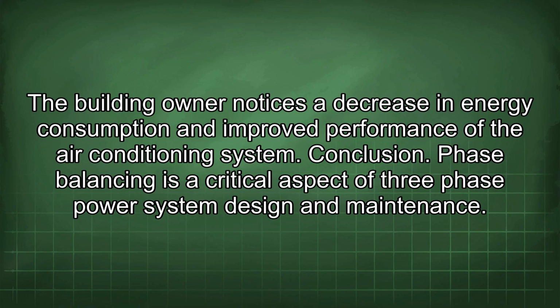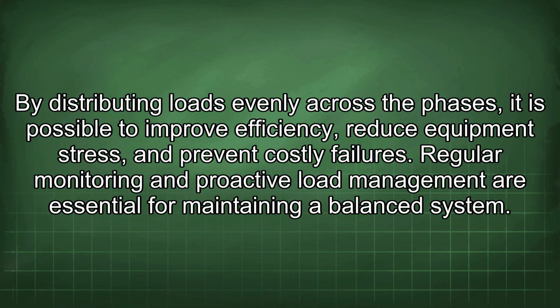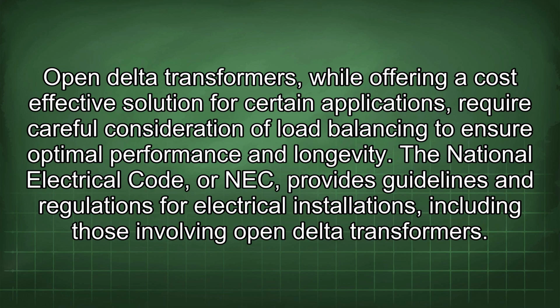Conclusion. Phase balancing is a critical aspect of three-phase power system design and maintenance. By distributing loads evenly across the phases, it is possible to improve efficiency, reduce equipment stress, and prevent costly failures. Regular monitoring and proactive load management are essential for maintaining a balanced system. Open delta transformers, while offering a cost-effective solution for certain applications, require careful consideration of load balancing to ensure optimal performance and longevity.